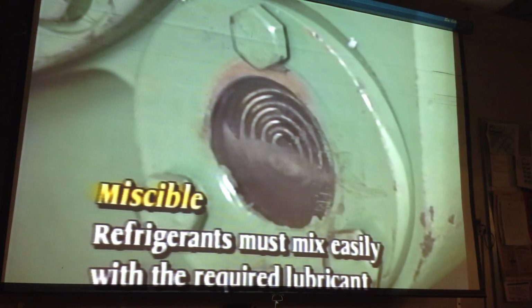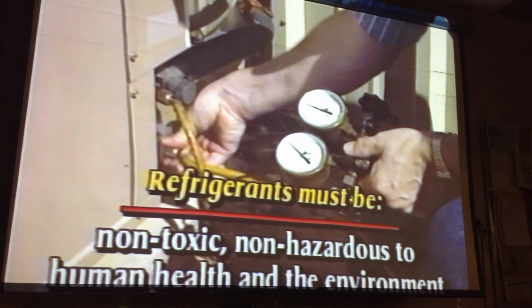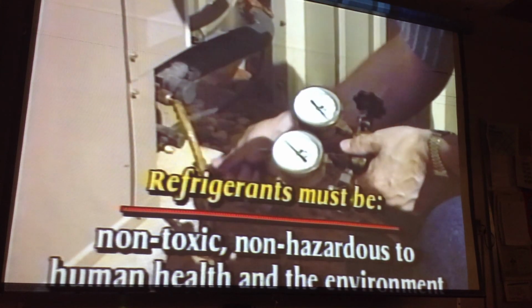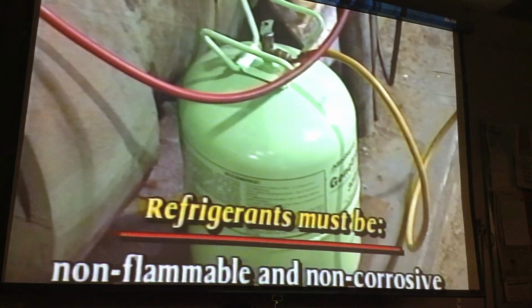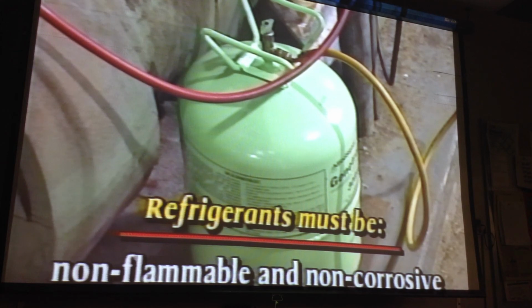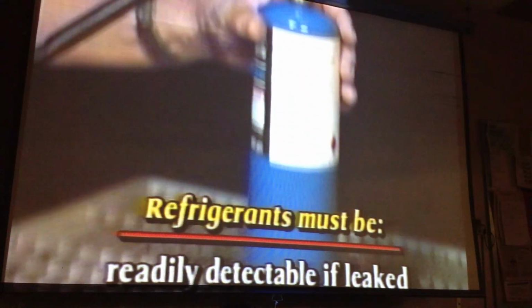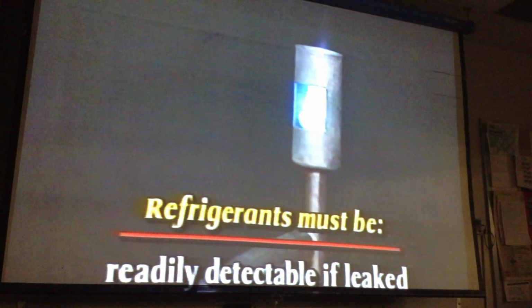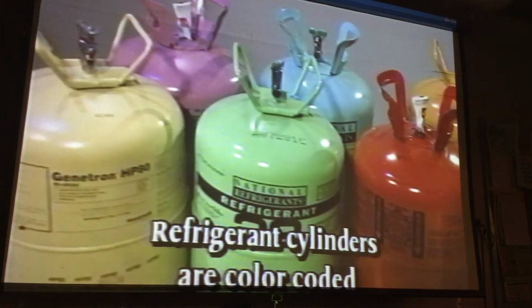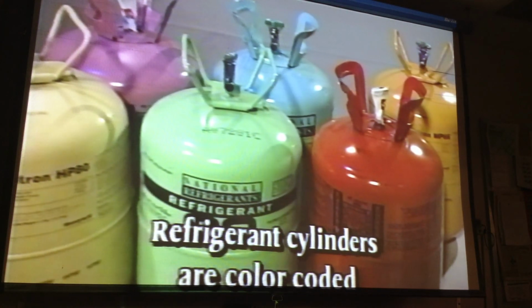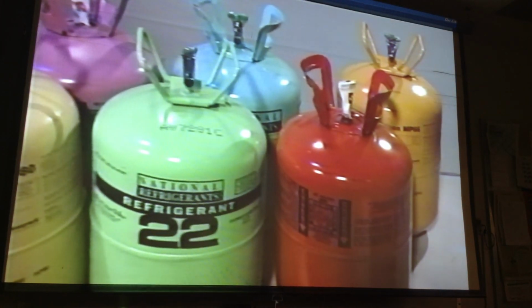All refrigerants must be miscible, that is, they must mix easily with the required lubricant. They must be non-toxic, non-hazardous to human health and the environment, non-flammable, non-corrosive, and they must be readily detectable if leaked. Refrigerant cylinders are color-coded to indicate the type of refrigerant they contain.